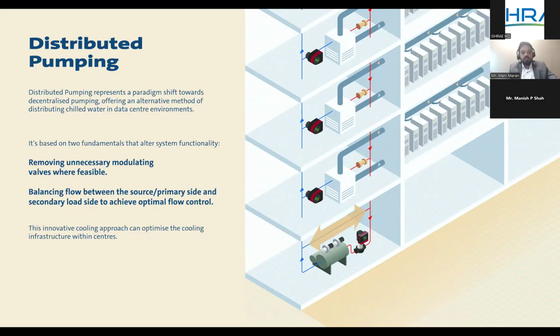So this innovative cooling approach is not only helping to save pump energy and system energy. In another way, the data center is an application where we have to keep adding modules when the load increases. Distributed pumping brings the flexibility of adding a module whenever your load increases. That's the additional advantage distributed pumping can bring, and it adds value to the data center design. Let's go into detail when we see the system design.